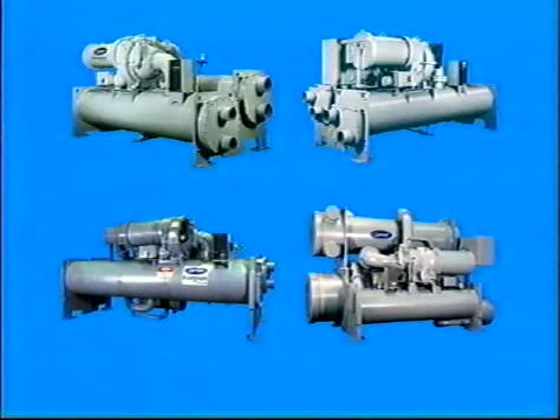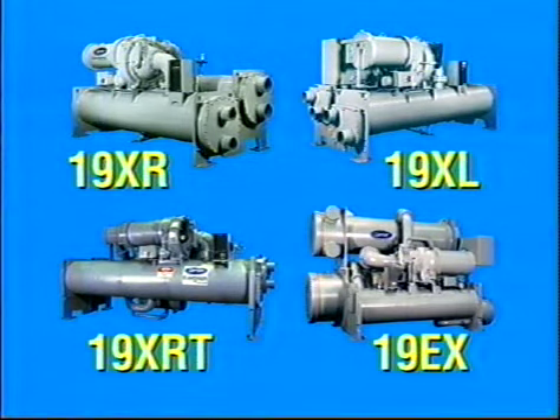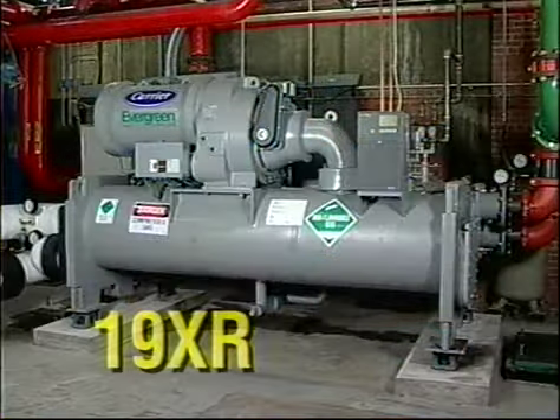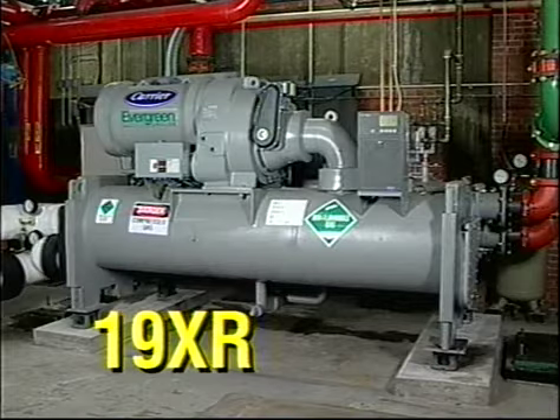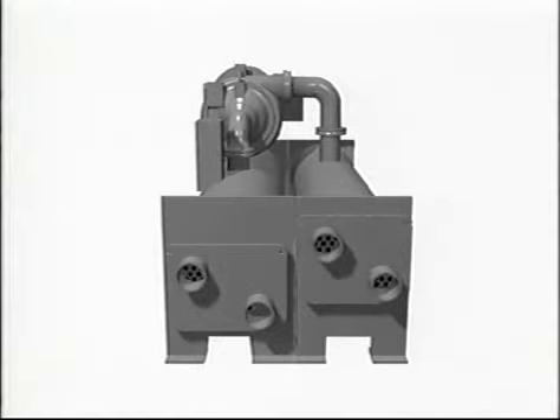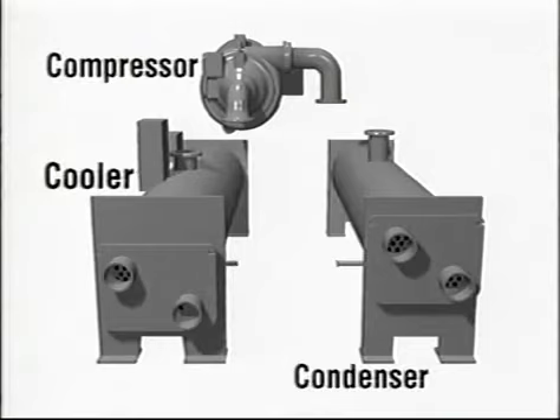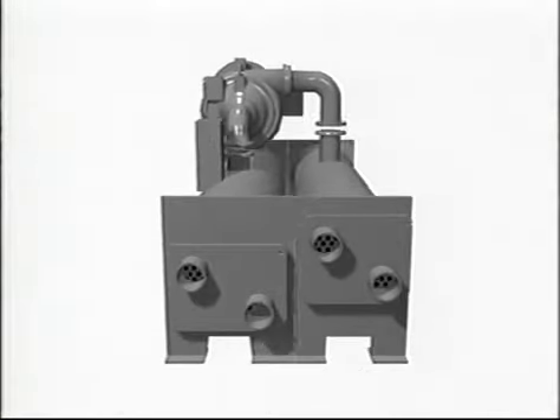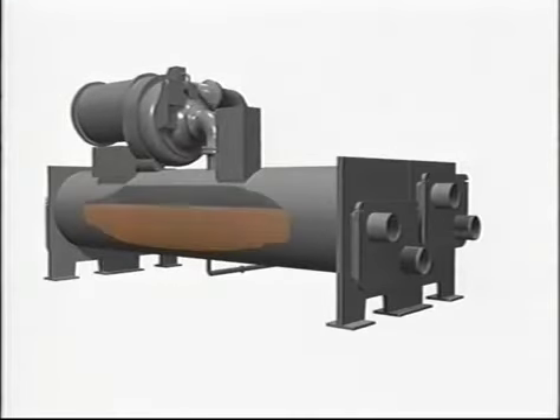19 series machines such as the XR, the XL, the XRT, and the EX vary in size and tonnage, but are similar in operation. So, for simplicity then, let's just consider the 19XR hermetic centrifugal chiller. The chiller has three main parts: the cooler, the condenser, and the compressor. The compressor is mounted on top of the cooler. The cooler is really just a big tank with a lot of tubes running through it.